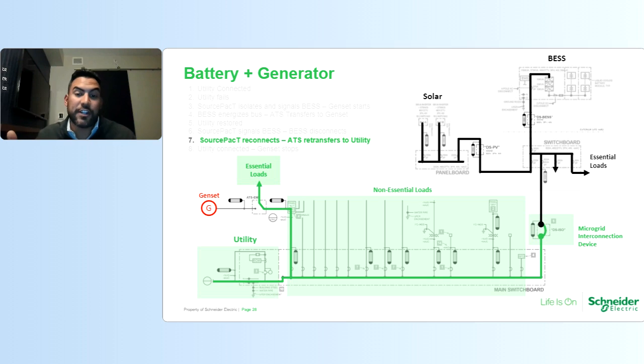The microgrid interconnection device here operates in an open transition. So from the moment that we lose power, there will be a momentary outage where we disconnect and have the energy storage system come online. And then vice versa, when utility is restored, it would operate in an open transition.